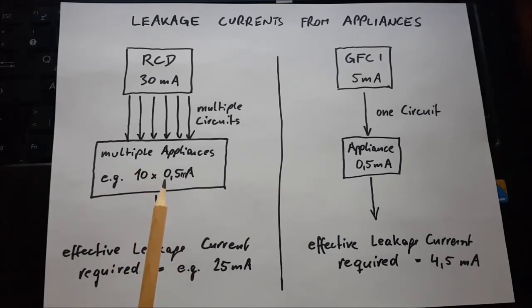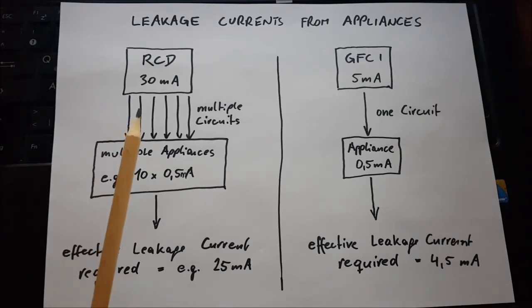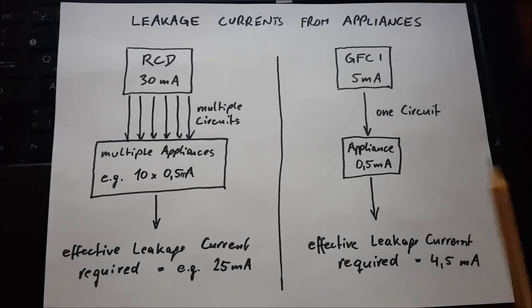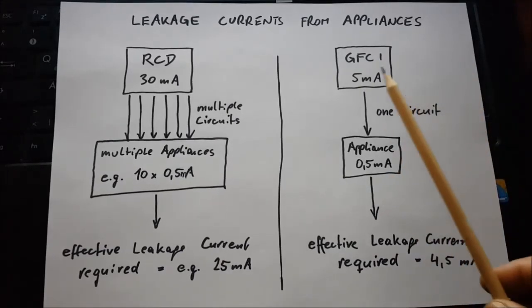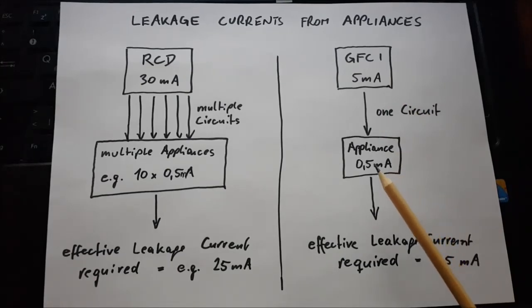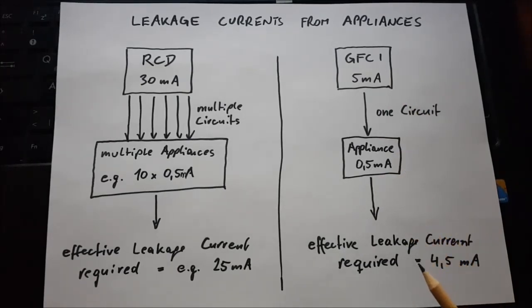So my leakage current behind that RCD coming from appliances is already 5 milliamps. So that will reduce the active range of this RCD already by 5 milliamps. So how much leakage current does a human have to add to trip that RCD? In this case, maybe 25 milliamps. When we look at the GFCI circuit, we have 5 milliamps, one appliance, 0.5 milliamps. So in this case, extra leakage current has to be around 4.5 milliamps.